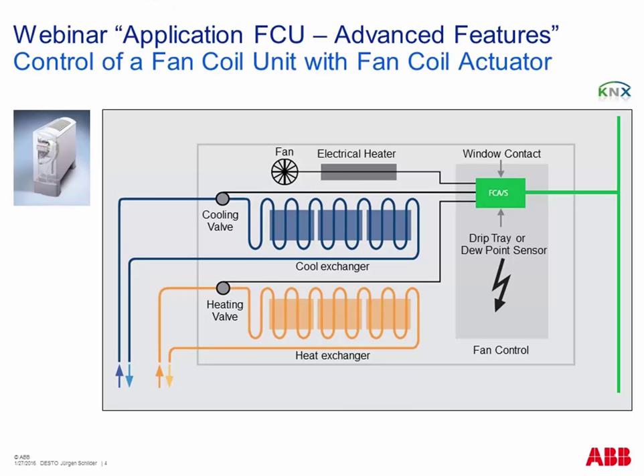Fancoil unit control — here is a symbol picture of a Fancoil unit. This four-pipe system means we have a heat exchanger and a cool exchanger. The system is supplied either with cold water or with warm water. We control with our fancoil actuator the valves — heating or cooling valve — and additionally the speed of the fan. It can also be a two-pipe system, with only one or two pipes coming in and going out, but always the same valve control and fan speed control.